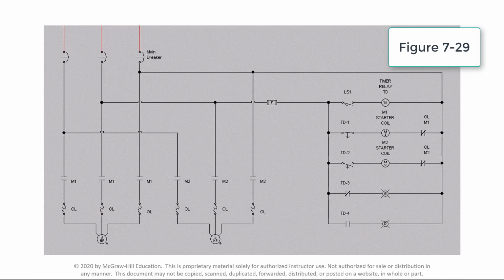This video demonstrates the operation of an off-delay timer with both instantaneous and timed contacts. Some types of timer relays come with a combination of timed and instantaneous contacts in both normally open and normally closed configurations. The instantaneous contacts are controlled directly by the timer coil, as in a general-purpose control relay.